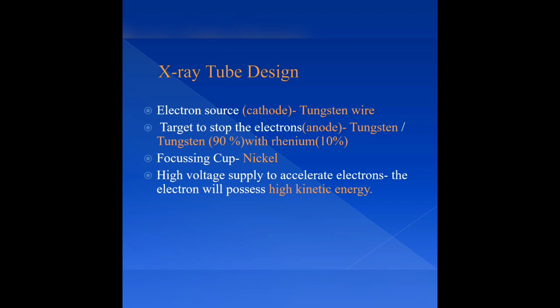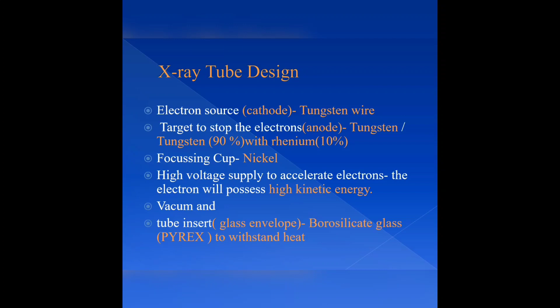Then this X-ray tube is a vacuum tube insert. The cathode and the anode, everything is inside a glass envelope, and the material of this glass envelope is borosilicate glass, otherwise known as Pyrex glass. The peculiarity of this glass is that it can withstand heat. As I said in my previous slide, about 99% of heat is produced, so in order to withstand that heat, this is formed of Pyrex glass, that is borosilicate.